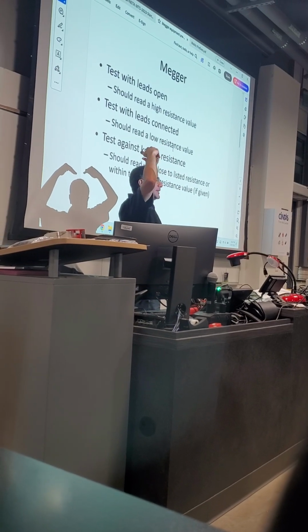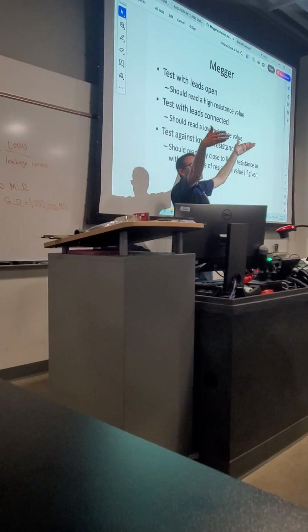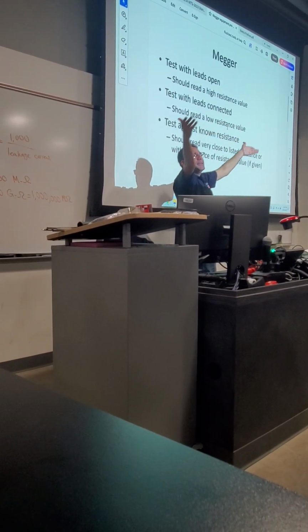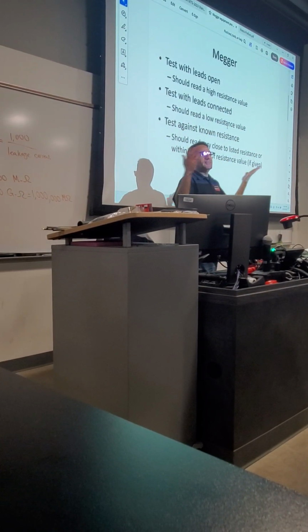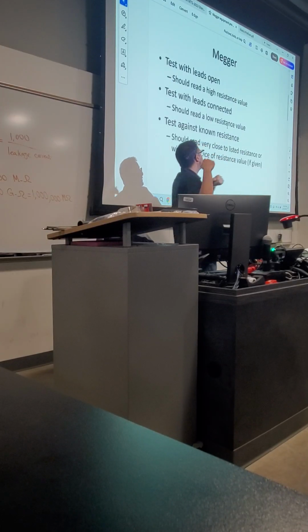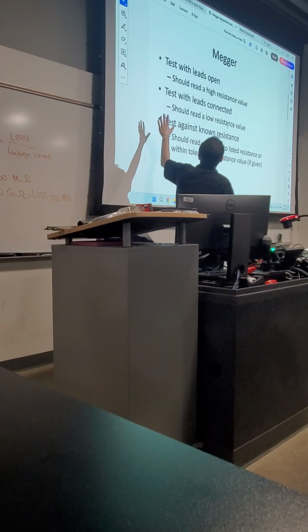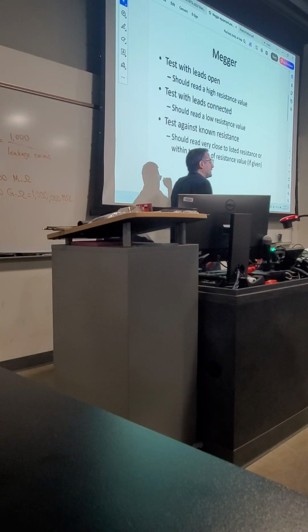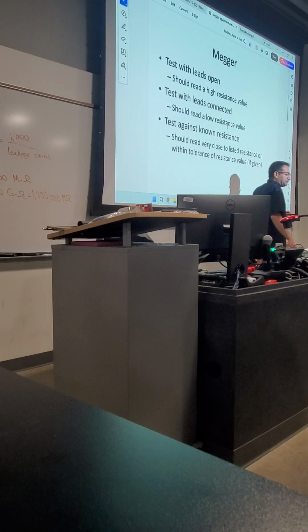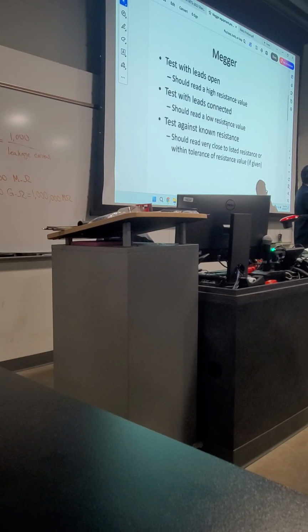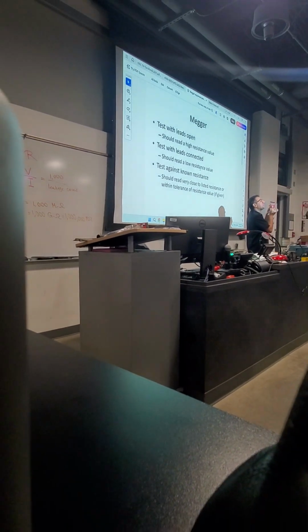Low. Short, right? The minimum reading that you see depends on the test instrument. The minimum it can measure, below limit. You tell me what you see on the test instrument. And the last one is going to be testing against the known resistance. And that's what we have here. This one is 10 mega ohms. Again, capital M is mega, small m is milli.